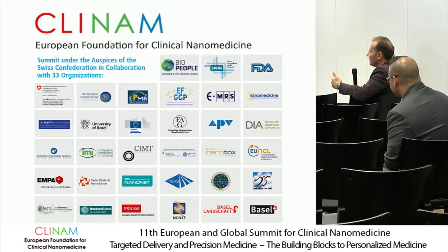But we would typically go to a lab, give a TRPS sample data, and they say, oh, can you explain why that's different than my Zetasizer? And my standard answer is, you better go and ask Malvern, because our answer is the right answer, because everything's totally calibrated routinely. And the DLS is just not quite a random number generator, but on a complex sample it actually is. So for exosomes, for instance, DLS is utterly inappropriate, and you still get people submitting it. So you have to go back to finding out the real measurement and comparing that with calibration.